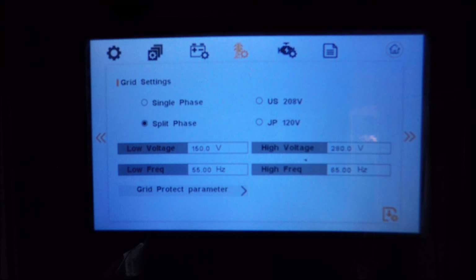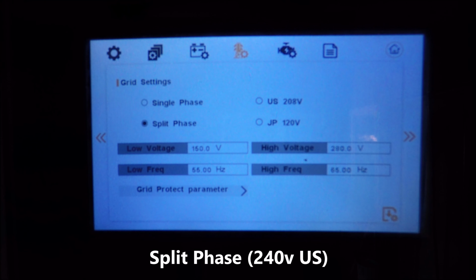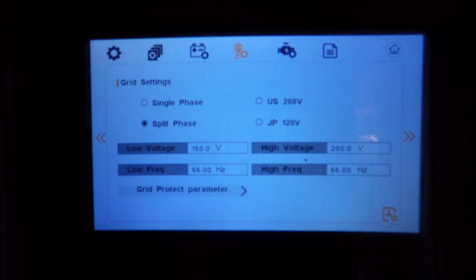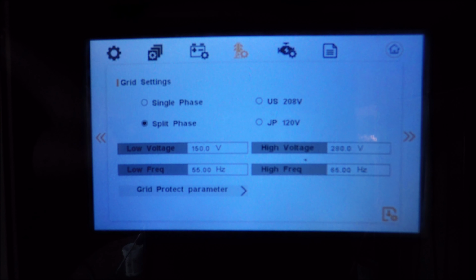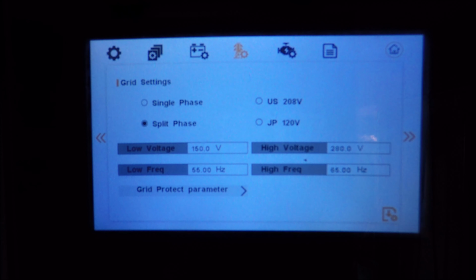We'll go back into our menu, and we'll go to grid setup. Under grid setup, for most US setups, we are going to select split phase. This is standard 240 volts with 120 volts on L1 and 180 degree phase to 120 volts on L2. This is the most common US setup. This will give you 240 volts across both phases. If you select single phase, the inverter will output 230 to 240 volts AC on both L1 and L2. Any 120 volt load would be damaged if you connected them to the inverter in this mode.